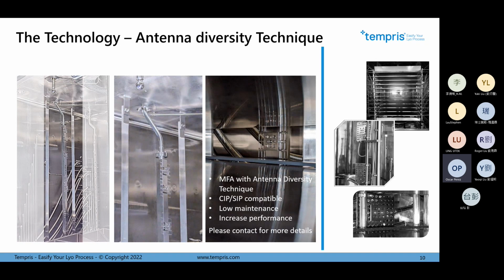Everything is fully integrated in a tube and kept at atmospheric pressure outside. The antennas are provided in 316L material with a roughness better than 0.8, easy to clean, and with a helium certificate, so everything is completely sealed to avoid any leak in the freeze dryer. On the right side, we have an example of the traditional antennas, normally for retrofit solutions. We can offer a rod with some clamps, and we can attach these antennas in parallel to, for example, any vertical CIP pipe. Or when it's a new freeze dryer, manufacturers also build special rods inside, always stainless steel 316L, to clamp these antennas.